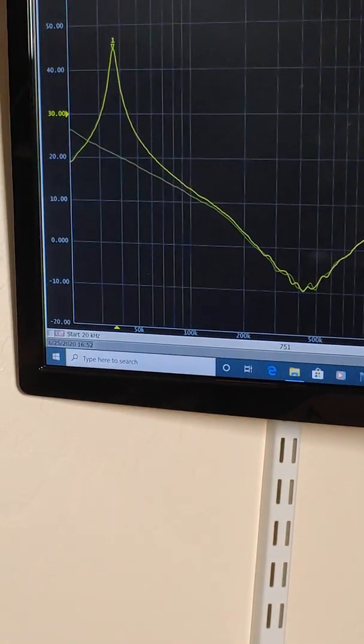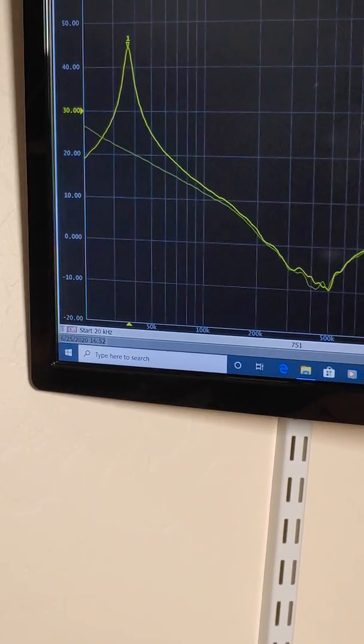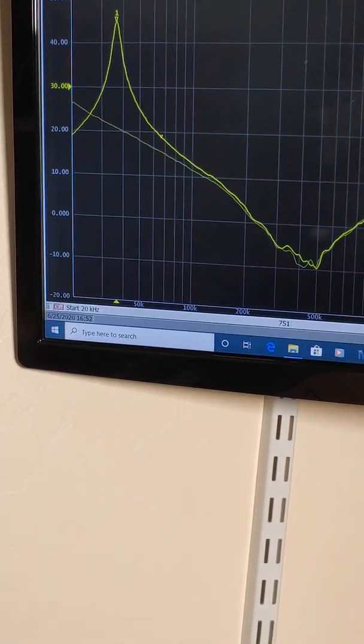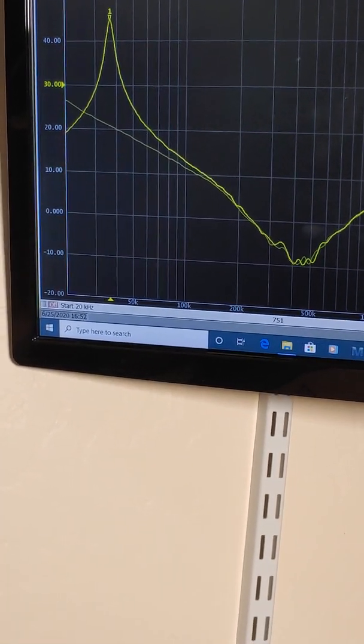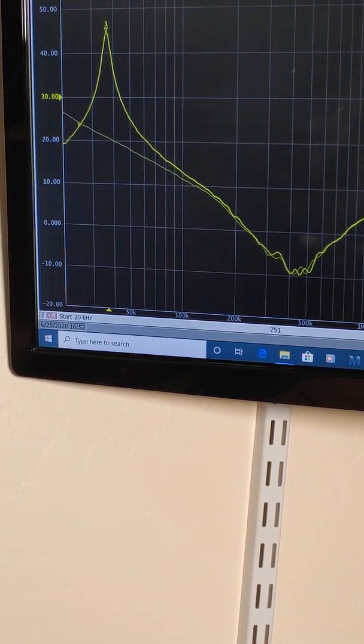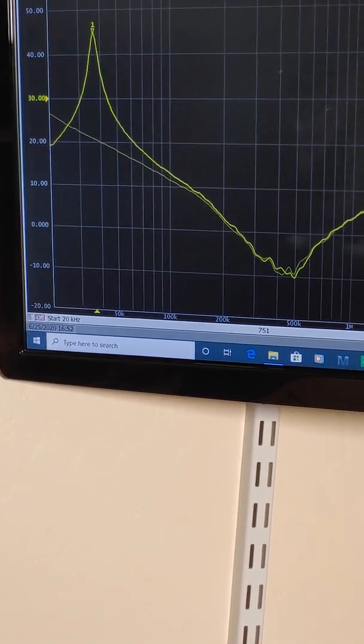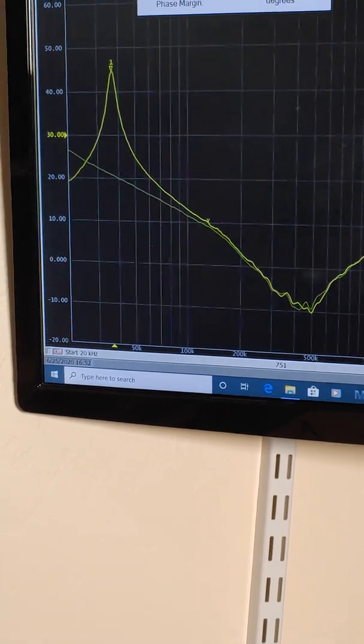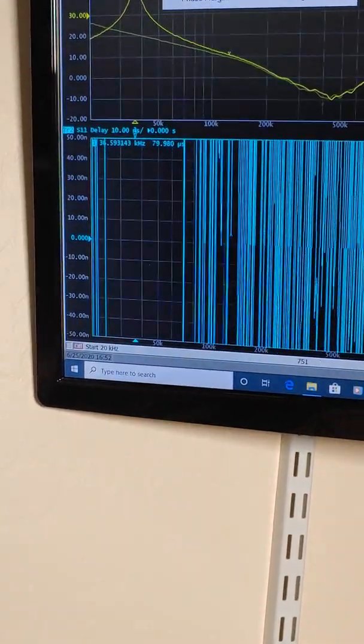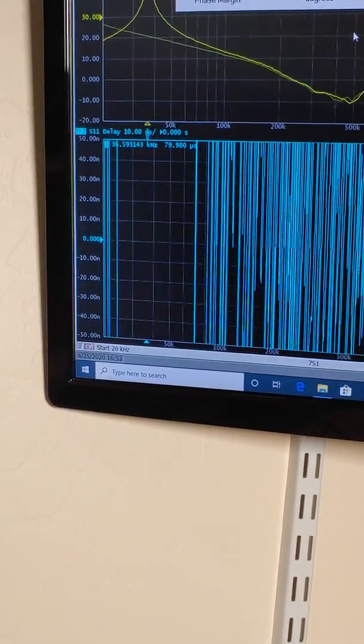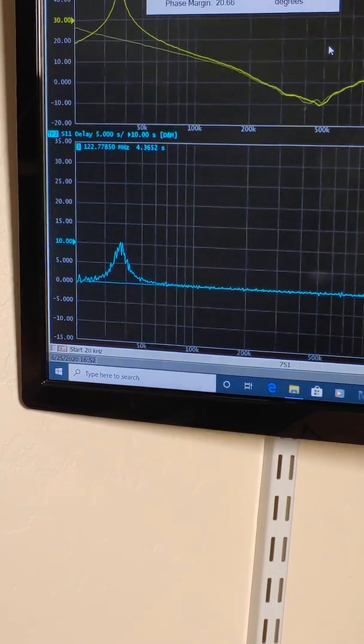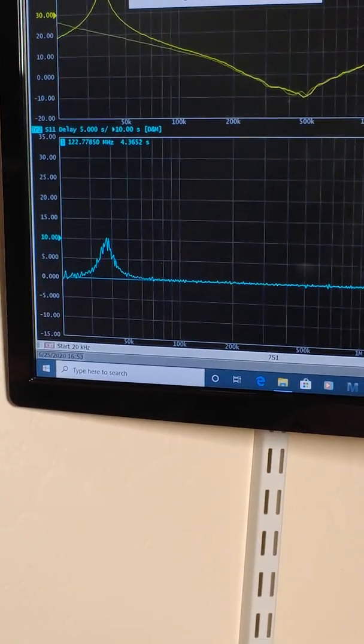So now I'm going to bring up the non-invasive soft stability margin tool. There it is, connected to the VNA, and it's connected. Use S11, because this is a one-port measurement. Measure stability margin, and you can see it's going to rerun those sweeps.